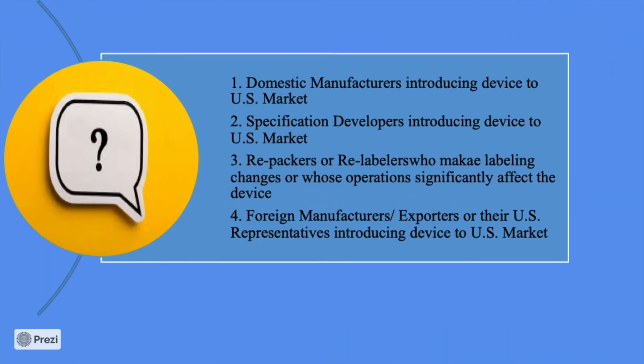Who can submit a 510(k)? Domestic manufacturers who want to introduce a device in the US market, specification developers, repackagers or relabelers who make labeling changes or whose operations significantly affect the device, and foreign manufacturers, exporters, or their US representatives who want to introduce the device in the US market.